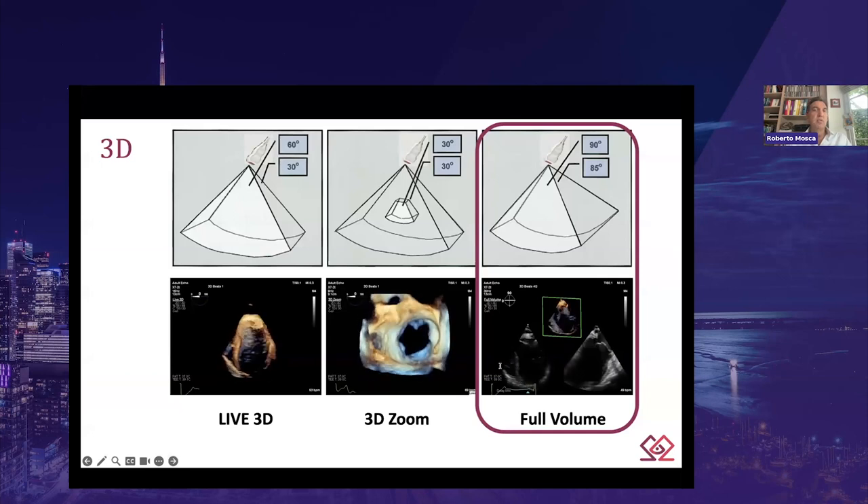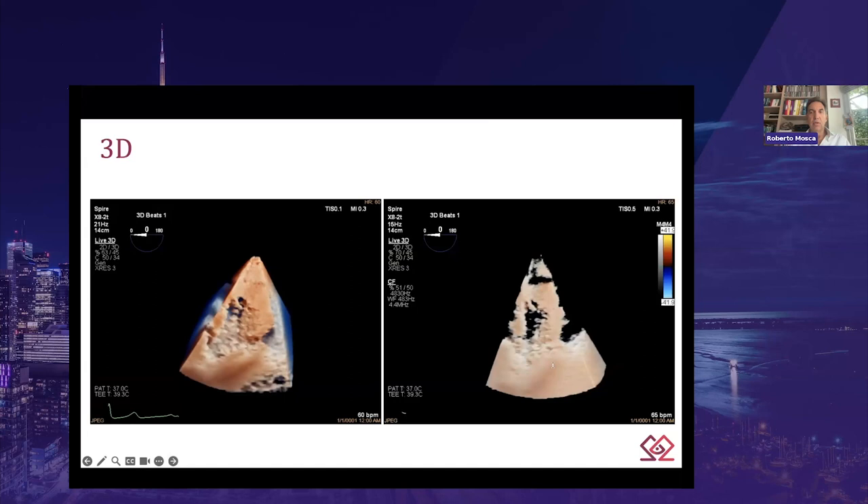3D zoom displays a focused volume of interest defined by a truncated slice of an arbitrary sector angle and greater detail, with or without ECG gating. Real-time 3D zoom is indicated for acquisition of valves and smaller structures such as thrombus or masses. Full-volume 3D combines a series of sub-volumes acquired with ECG gating to create a final, larger, reconstructed full-volume image. The 3D full-volume acquisition is the only imaging modality that can capture the entire left ventricular volume at a sufficient frame rate — 20 Hz or more — allowing dynamic assessment.